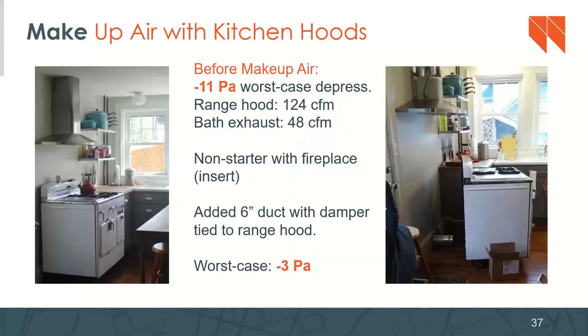The strategy for this one was to have it come underneath the very warm stove, as a kind of poor man's tempering. I've seen this on passive house projects as well; that's the gist of it. You want to have the makeup air coming in close to the heat source, i.e. the stove or range or whatever, that is triggering the need to have makeup air, to have that damper open in the first place. I suppose in very cold climates, some kind of duct heater might come into consideration for the design. But at least in our neck of the woods, climate zone 5, 4, even 6, this strategy is what we see most often.